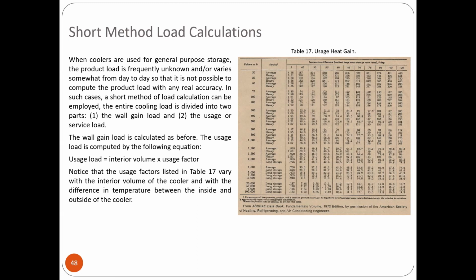The wall gain load is calculated as before. The usage load is computed by the following equation. Usage load is the interior volume times the usage factor. Notice that the usage factors listed in Table 17 vary with the interior volume of the cooler and with the difference in temperature between the inside and outside of the cooler. It's called a cooler, okay? These are coolers, not freezers.